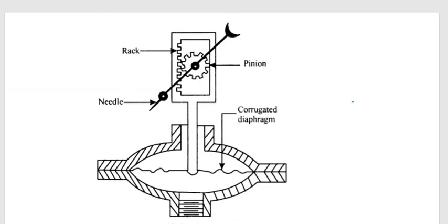As you can see in the drawing, here is a rack with a pinion, this is a needle, and below is a corrugated diaphragm. When pressure is applied here, it causes this diaphragm to move up, and this upward movement of the diaphragm causes the pinion and the rack to have a particular movement, thereby causing the needle to move on a scale, and therefore the pressure reading can be noted.